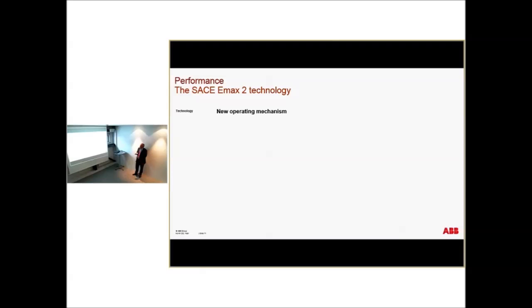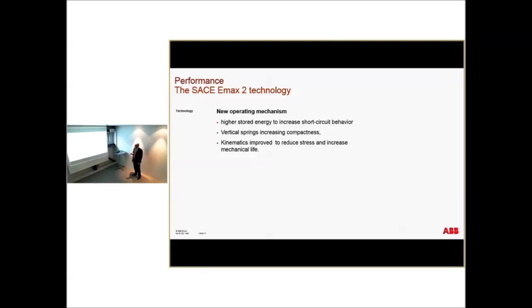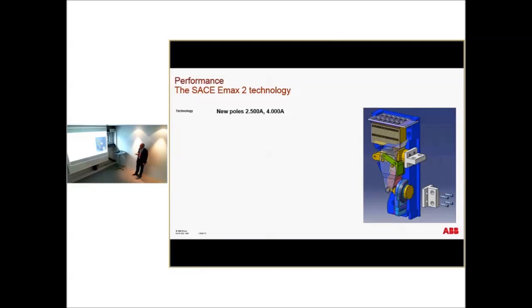Again, this is an interesting slide that shows exactly the work we have done in order to improve the capability of the breaker itself. We redesigned completely the stored energy mechanism in order to increase the breaking capacity. You have now vertical springs, also we reduced the space inside the breaker itself. And we reduce the stress and increase the mechanical life. So this was a big redevelopment.